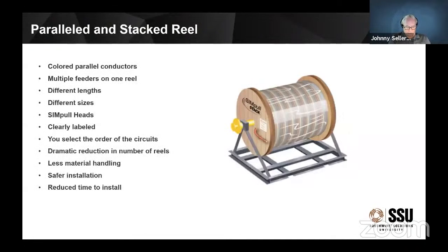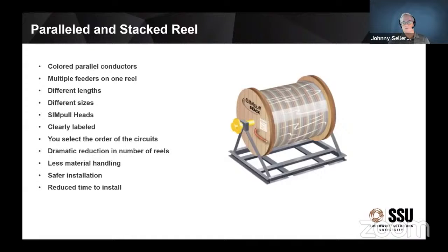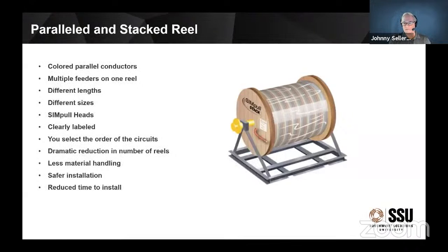I had a class recently where I asked who's been using stacked reels, and several already had. I asked what's the most number of circuits they'd ever put on a reel, and one foreman said he put 17 circuits on one reel once. He set it up in front of the MCC in the electrical room and pulled out all those feeders off one reel. Imagine 17 feeders all on one reel — if you did that the old way, you'd have been handling multiple reels. That's the advantage of paralleling and stacking. We're going to be looking at wooden reels today, but we also have our sim reel — you can stack and parallel on that as well.